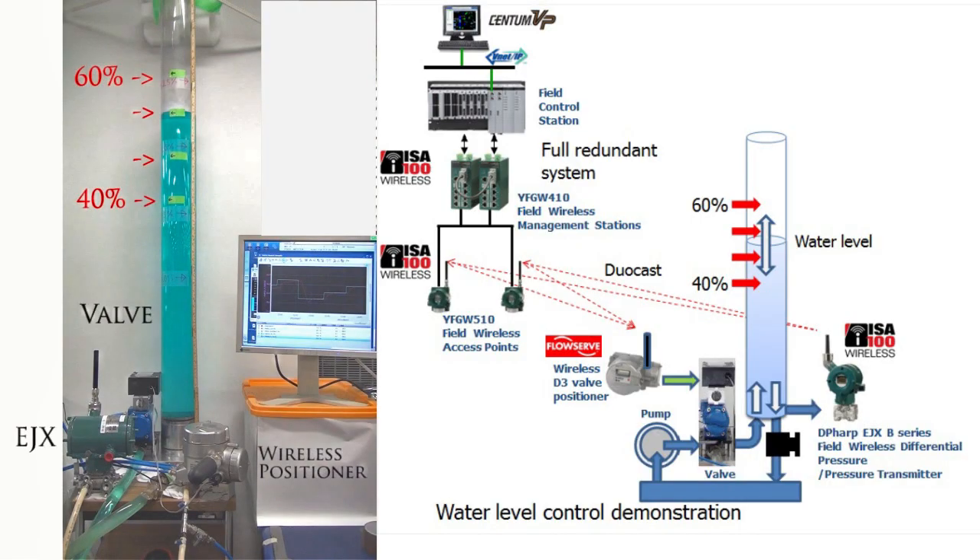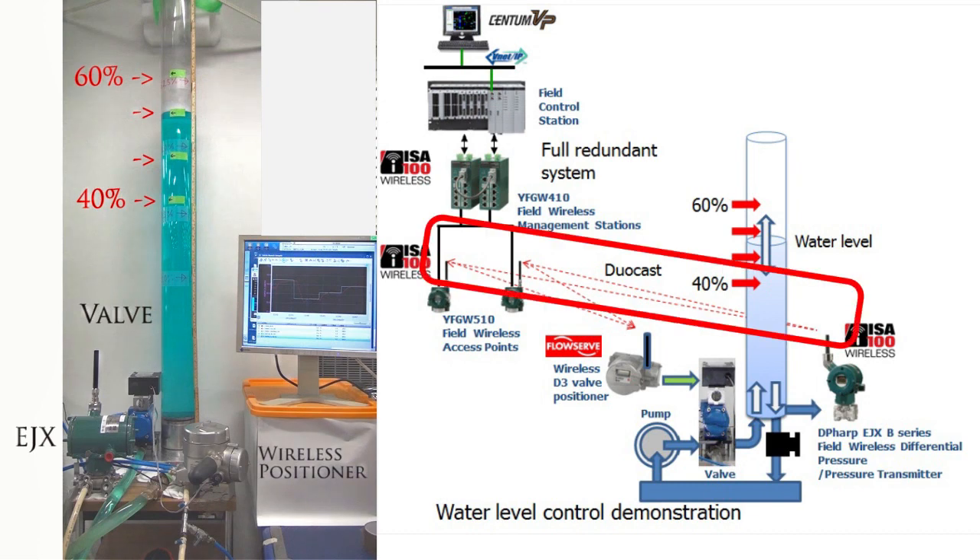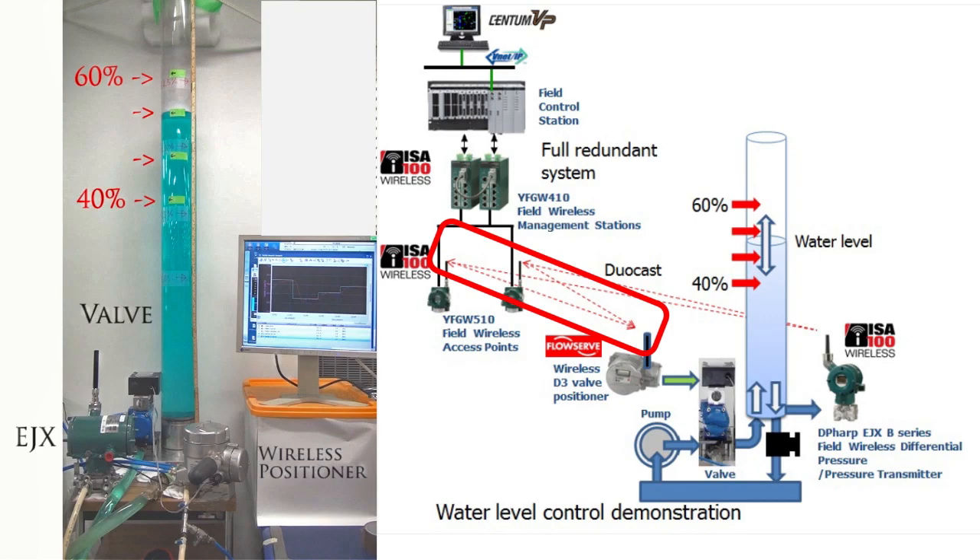This video shows ISA100 wireless control demonstration for the water level control application. This control is performed by the fully redundant wireless control system: redundant Centum VP controllers, redundant communication interfaces, redundant ISA100 gateway and system managers, redundant backbone routers, and redundant radio path. Duocast for pressure input, double unicast for valve control output.